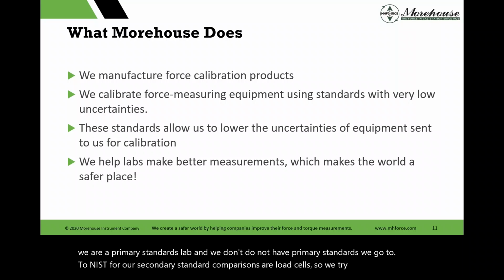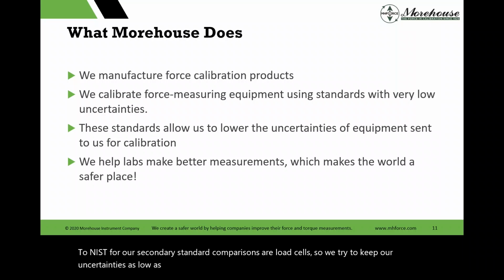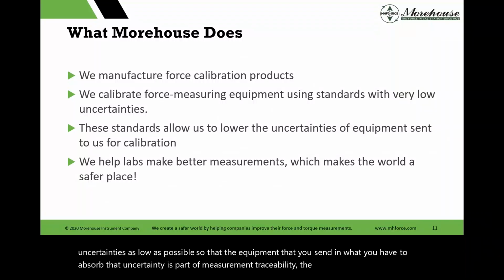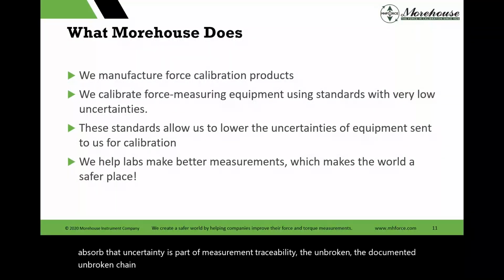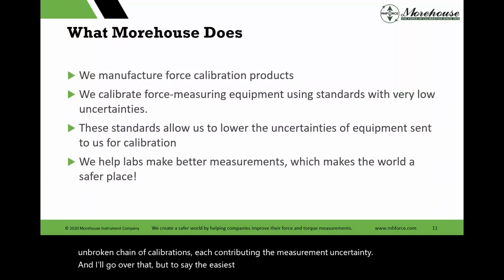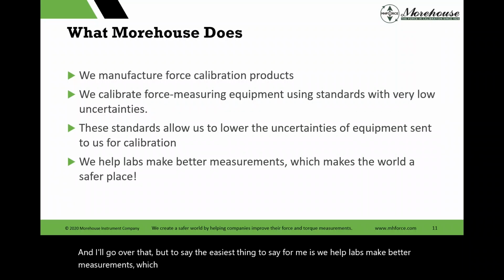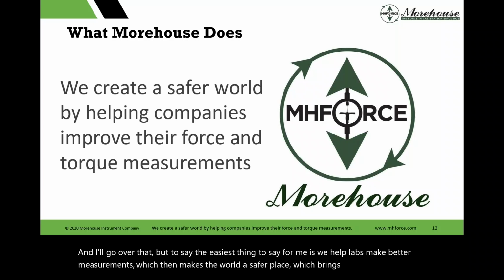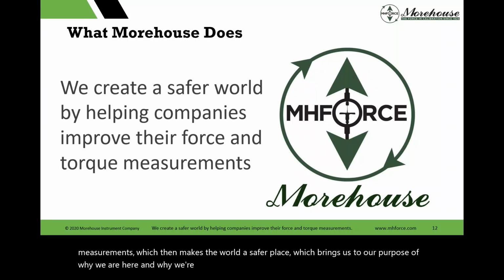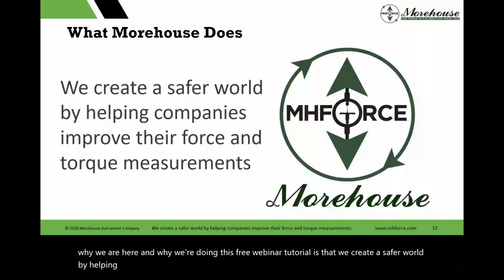So we try to keep our uncertainties as low as possible, so that the equipment you send in has to absorb that uncertainty as part of measurement traceability, the documented unbroken chain of calibrations, each contributing to measurement uncertainty. I'll go over that. The easiest thing to say is we help labs make better measurements, which then makes the world a safer place, which brings us to our purpose and why we're doing this free webinar tutorial: we create a safer world by helping companies improve their force and torque measurements.